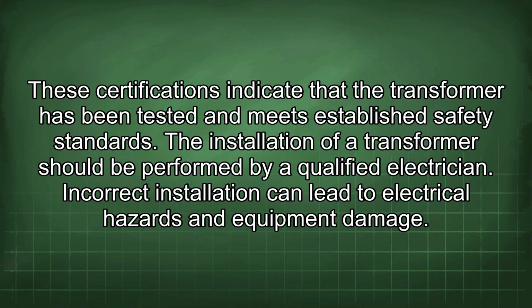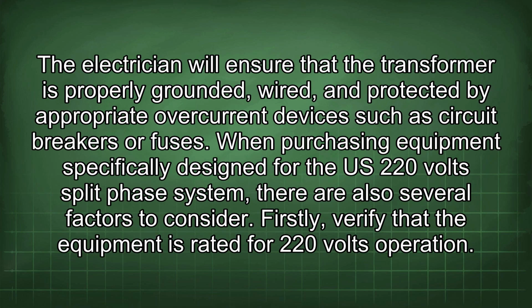The installation of a transformer should be performed by a qualified electrician. Incorrect installation can lead to electrical hazards and equipment damage. The electrician will ensure that the transformer is properly grounded, wired, and protected by appropriate overcurrent devices such as circuit breakers or fuses.